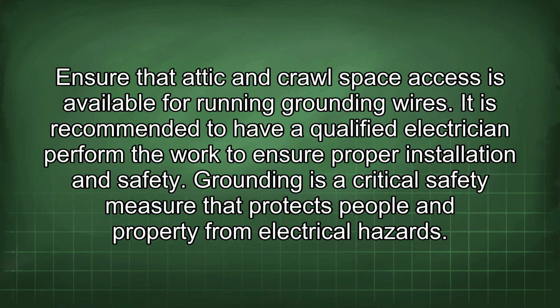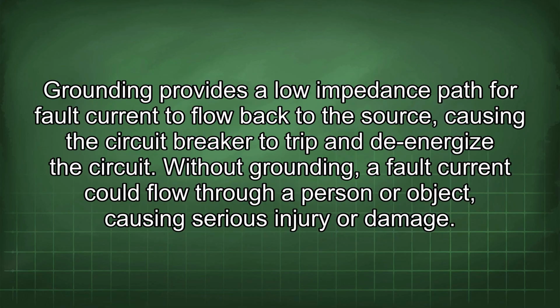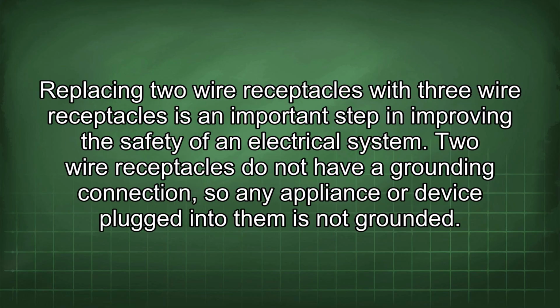Grounding is a critical safety measure that protects people and property from electrical hazards. Grounding provides a low impedance path for fault current to flow back to the source, causing the circuit breaker to trip and de-energize the circuit. Without grounding, a fault current could flow through a person or object, causing serious injury or damage. Replacing 2-wire receptacles with 3-wire receptacles is an important step in improving the safety of an electrical system.